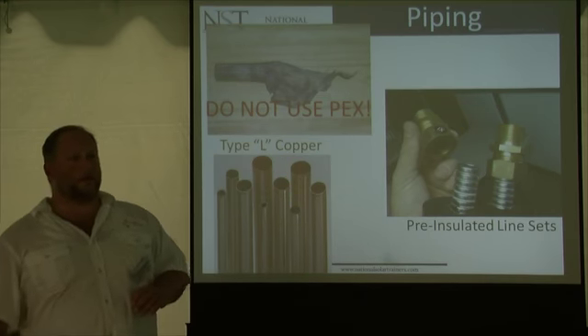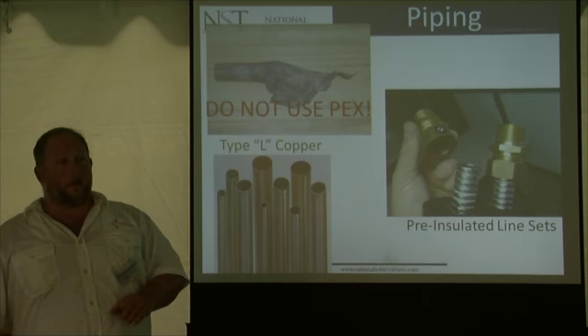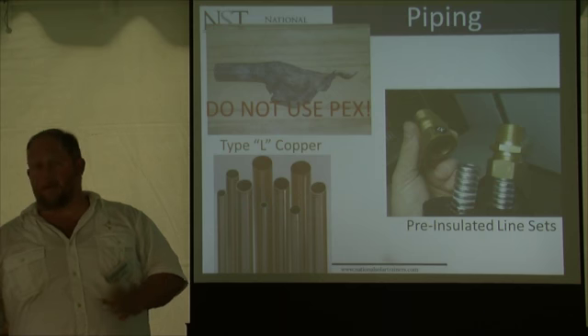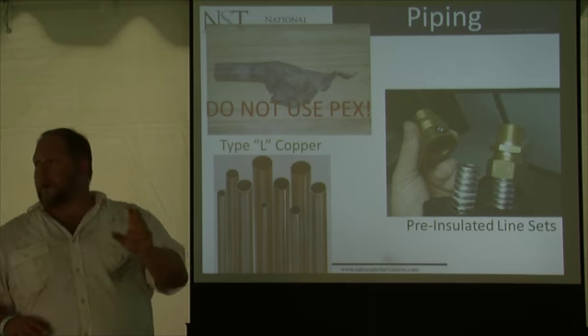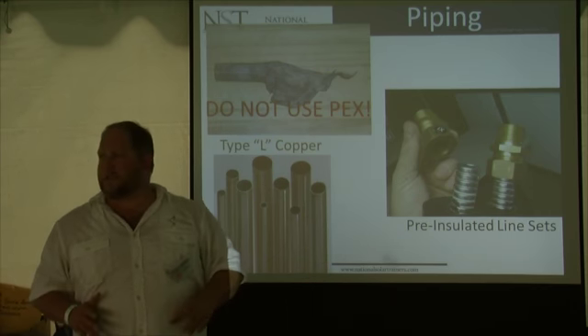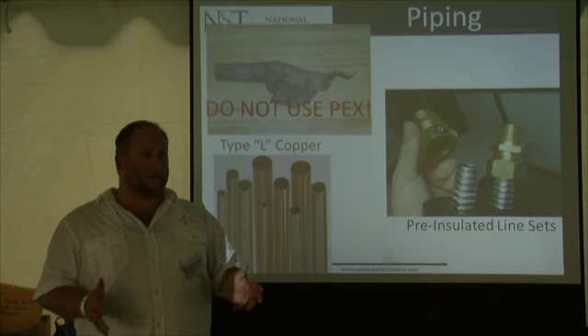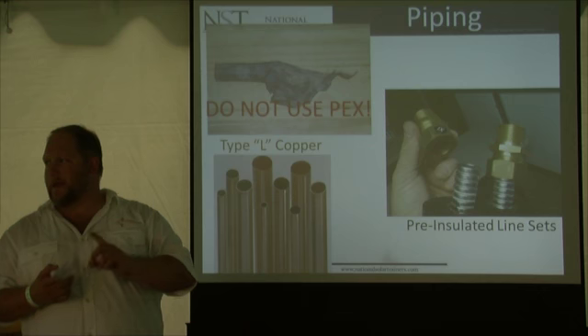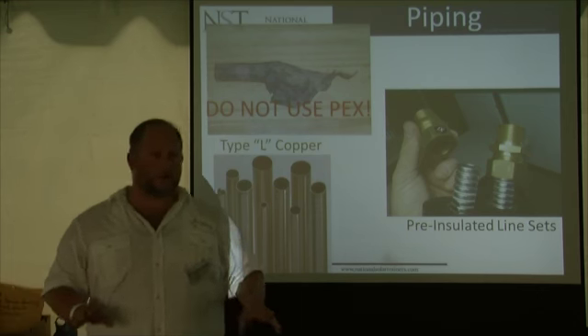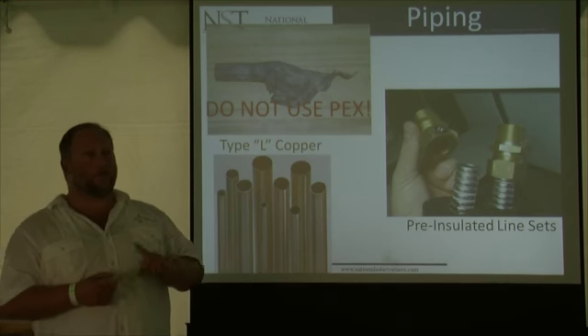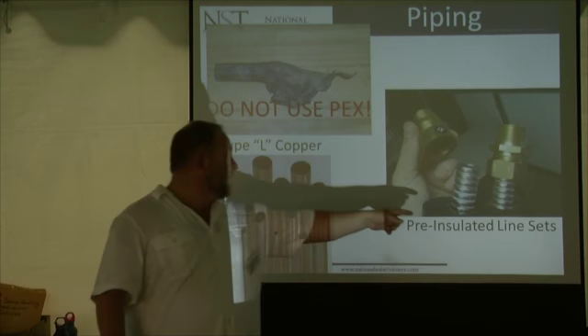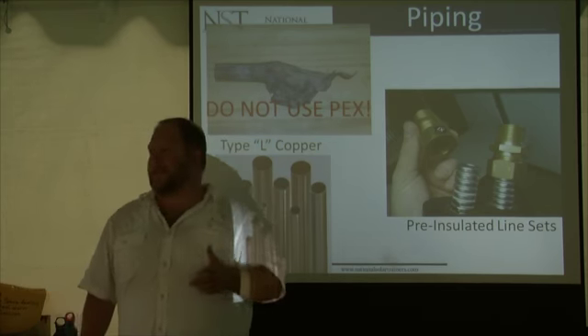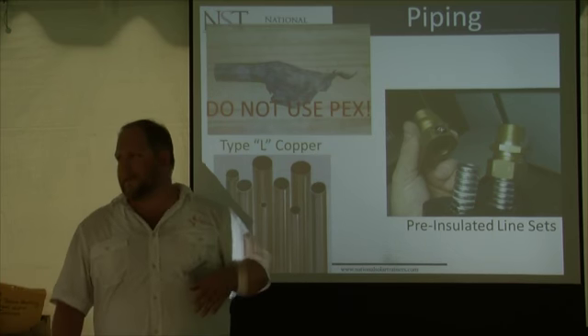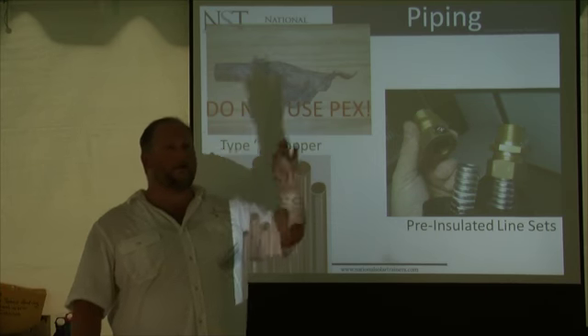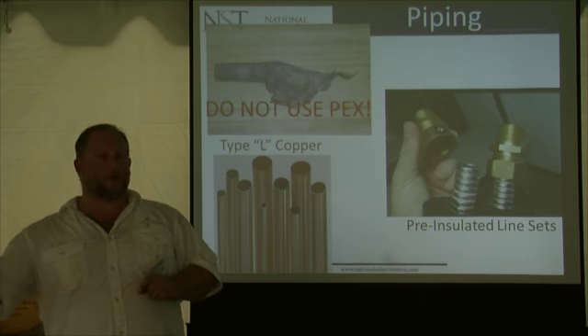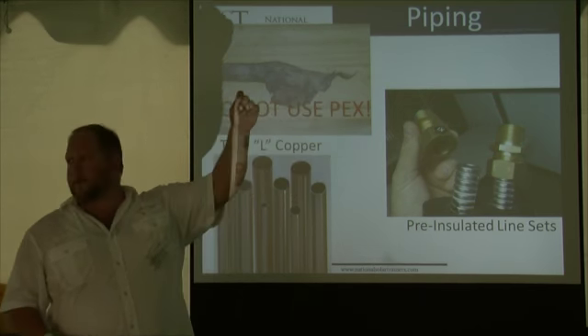Cost comparison: copper has a much higher upfront cost, about $11 a linear foot, but that includes the supply and return. You also have to consider that installation cost is the biggest cost in the whole thing - that's really the labor involved. With flexible stainless steel, that comes way down, not even close. It's also pre-insulated, with an insulated jacket and UV film around the outside of that insulation, plus a sensor wire embedded in the insulation that you can plug from your controller up to the collectors.